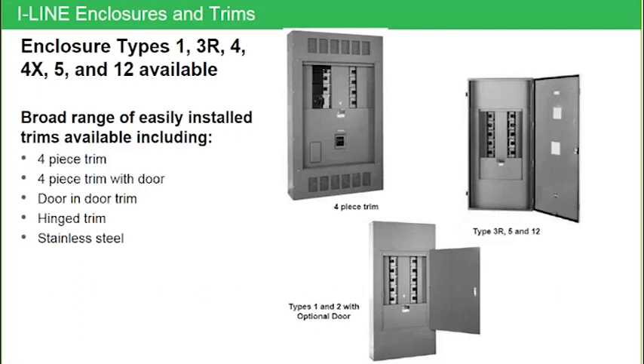So many of the larger I-Line interiors will be limited to not going into a fiberglass enclosure due to the weight. So you would probably for a 4X application, you would need to go with stainless steel.